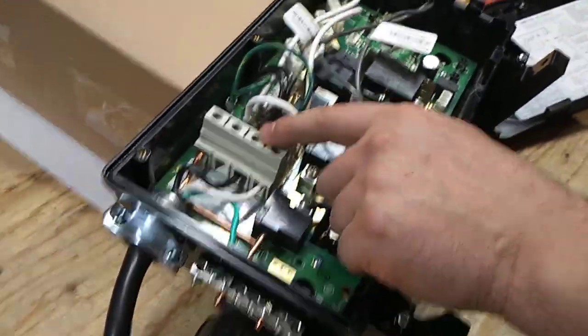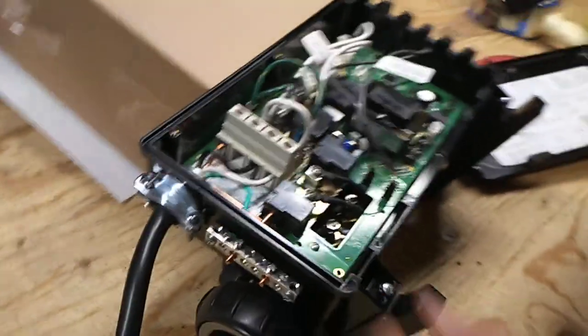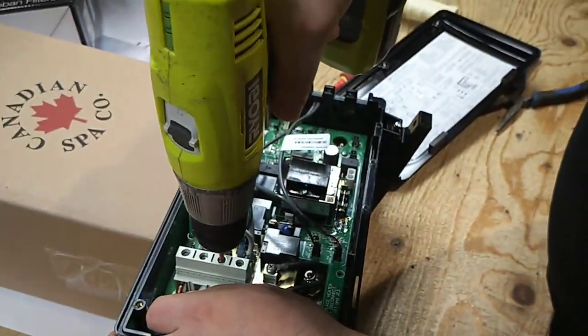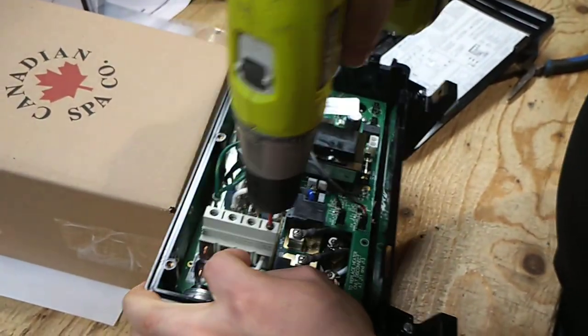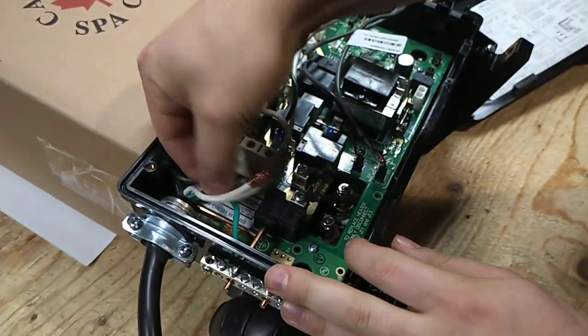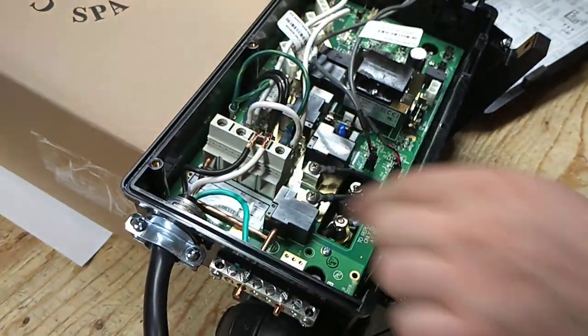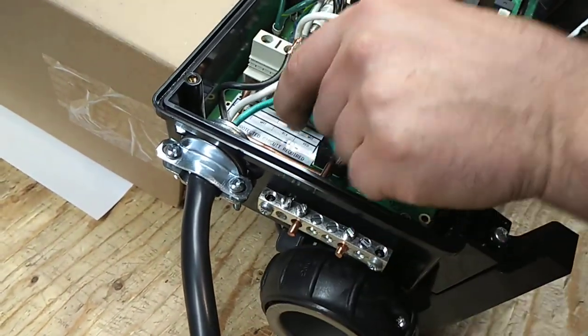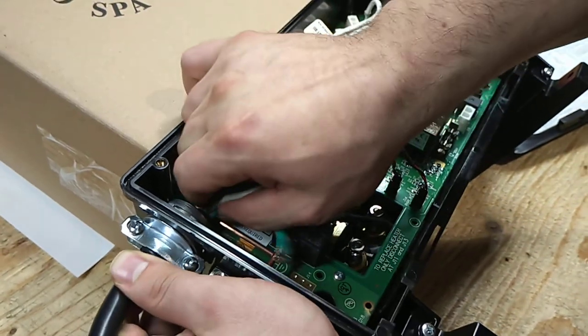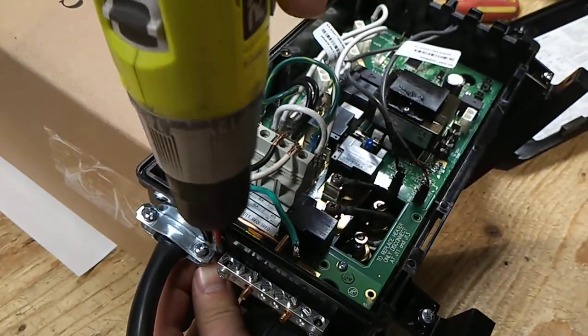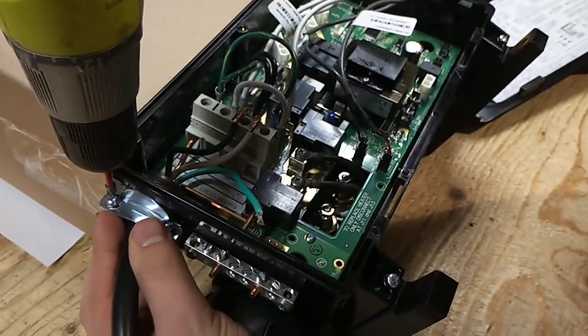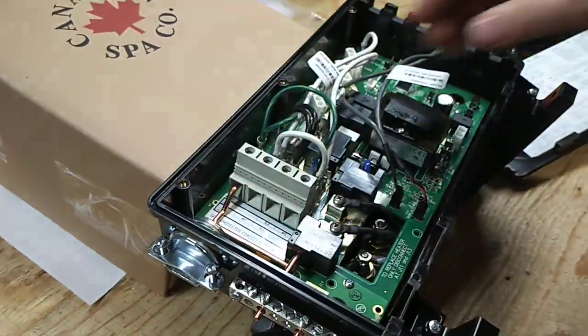We're going to look at our board and we're going to first start by looking at the terminal blocks. This terminal block here is already wired for 120. So this is the part your electrician is going to need to do. You're going to want to remove the current wires in there. Remove your neutral and your hot. Remove your ground over here. This allows you to now pull out the 120 volt wire.